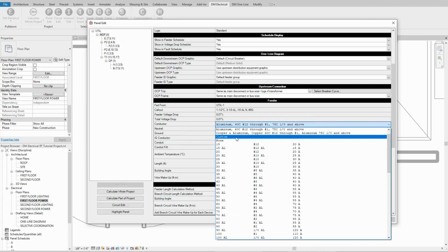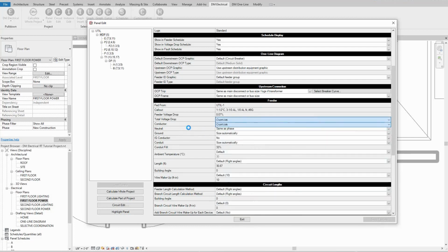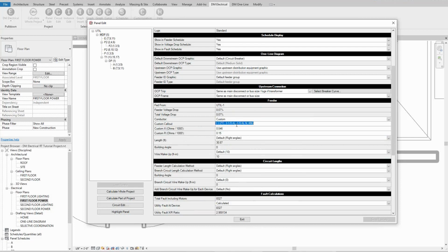We also added the custom wire size, where you can select custom, and then you can type in any sort of description that you want and give us any X and R values for your impedances that you want. One place where this is used is if you have a bus duct. You can say, okay, this isn't actually a wire, this is a bus duct. Then you go to the manufacturer and look up the bus duct impedances, which are usually much smaller, and you type those in. And then you have a bus duct modeled rather than a piece of equipment, or rather than wires.